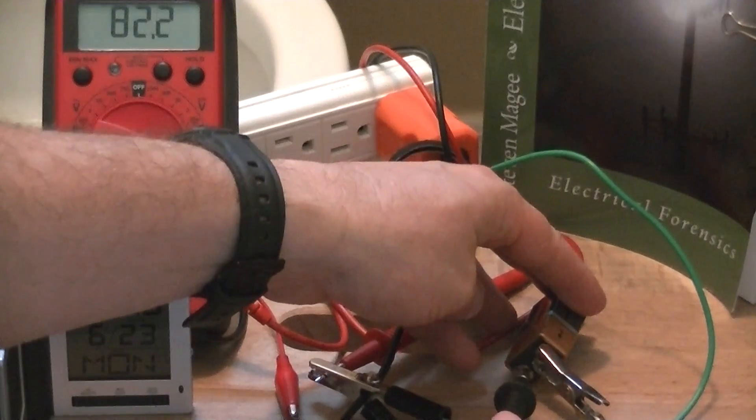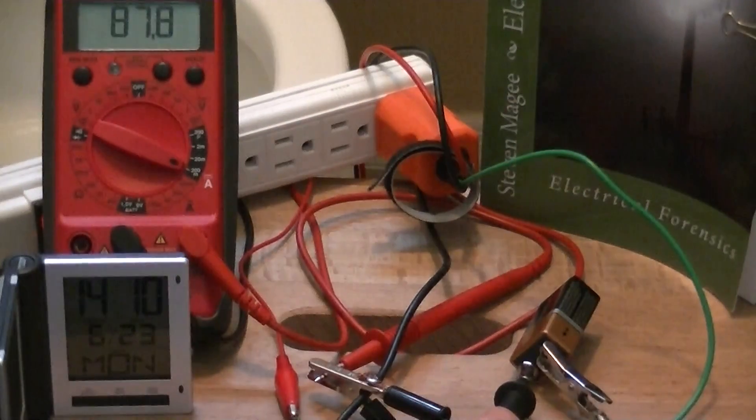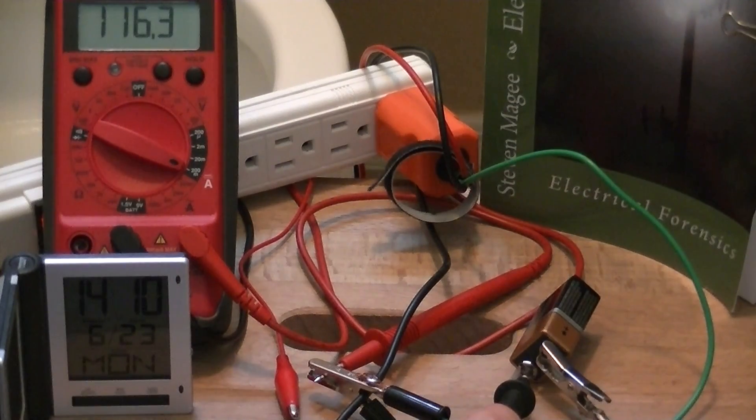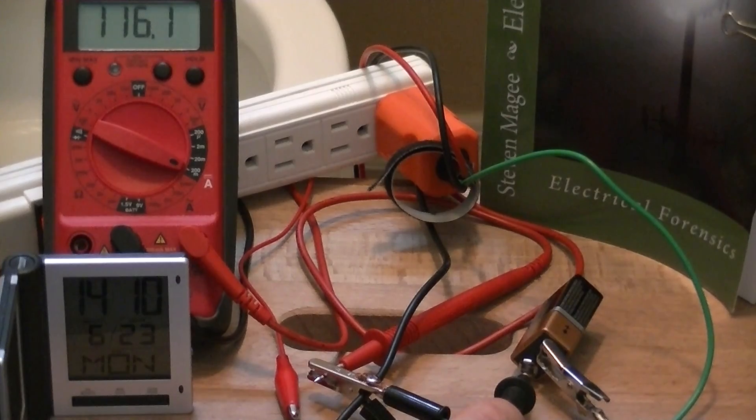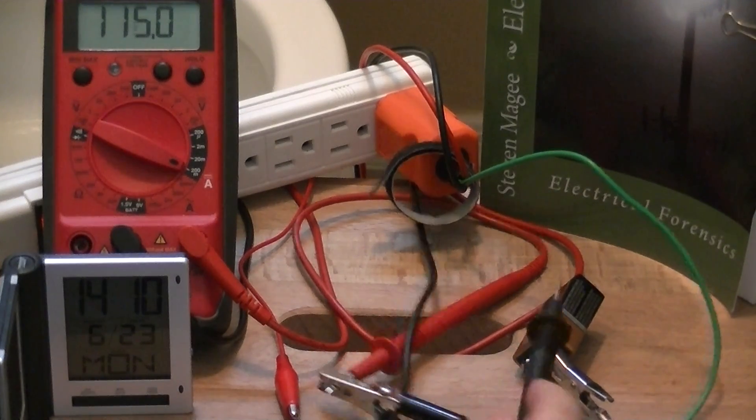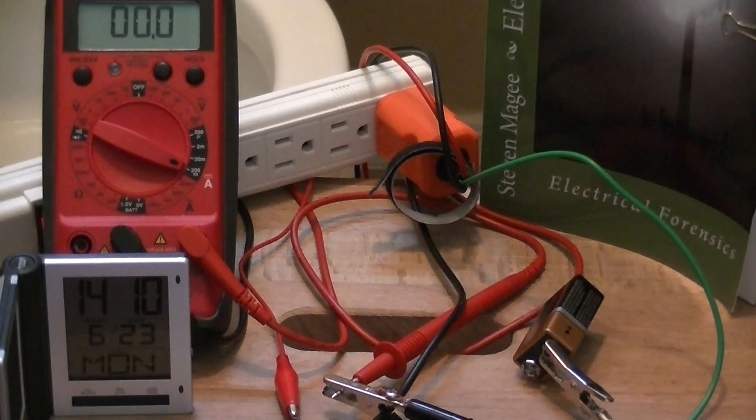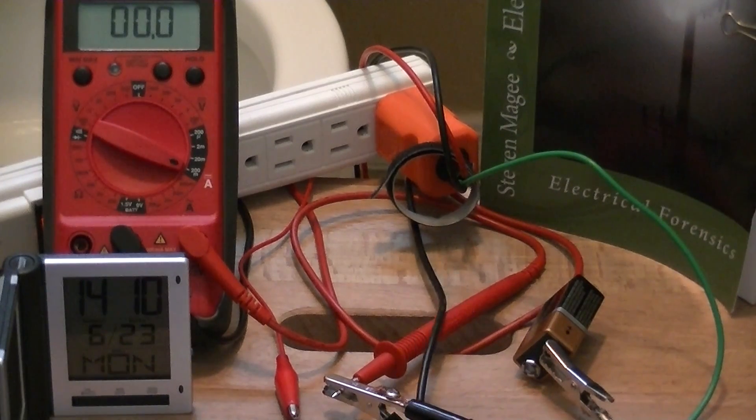And watch the display. You can see that we actually have 116 milliamps flowing between the home electrical grounding system and the non-electrified ground rod in the back garden. That tells us that we have a very good ground connection for doing our measurements.